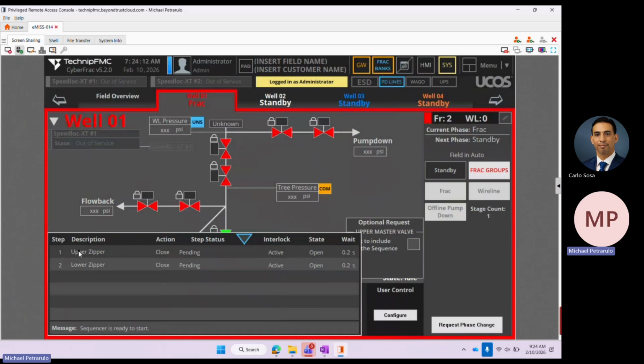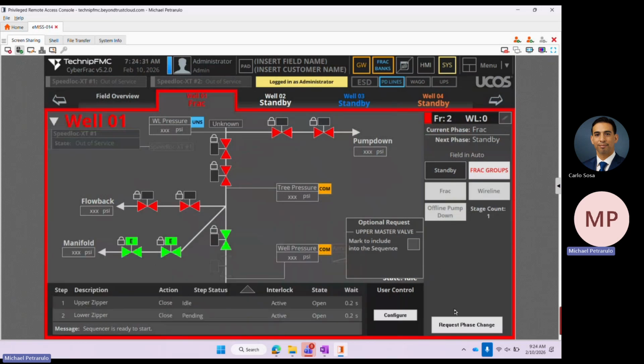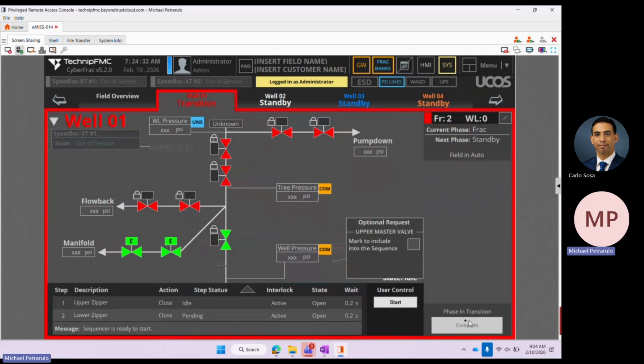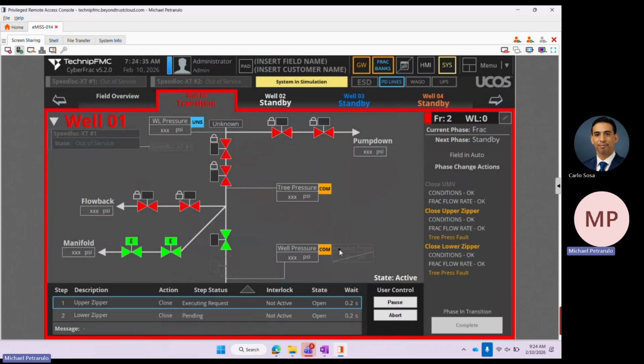So my sequencer is saying upper zipper, the action is going to be closed. And it currently has an interlock active, so I can't even touch it. And lower zipper is the next step, number 2. We're going to close this one. Once the sequencer is executed, the system will auto-complete and you're back in standby. So we can show this. If I hit request phase change, if I don't have any approval set, it'll just automatically execute. So like I said, the sequencer is moving everything for me. I don't have to touch a thing.